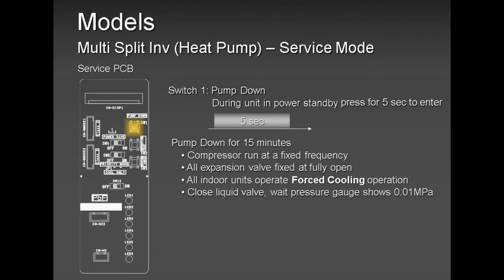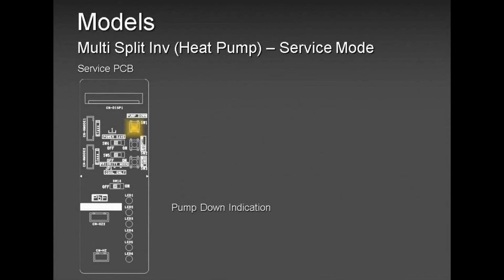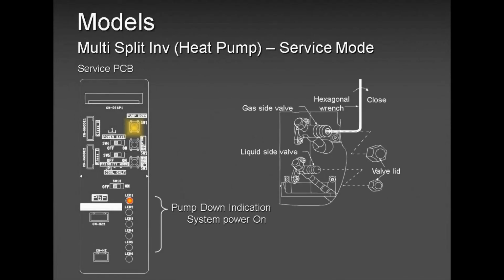And again, lack of oil, because of the job that I referred to, go back and check the story about that job site, the guys exceeded the limitations of the pipe and forgot to add refrigerant. So please keep in mind that when you exceed those pipeline limits, always remember to add refrigerant. It's either 0.22 or 0.33. The bigger the capacity, it's 0.33, the smaller the capacity, it's 0.22.